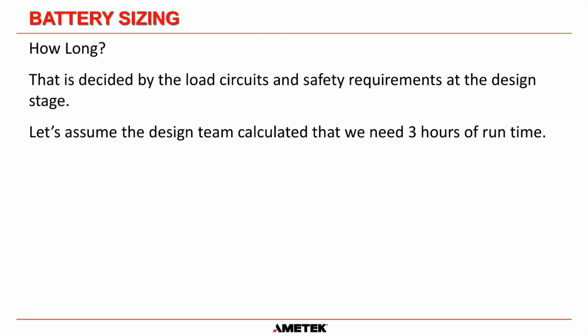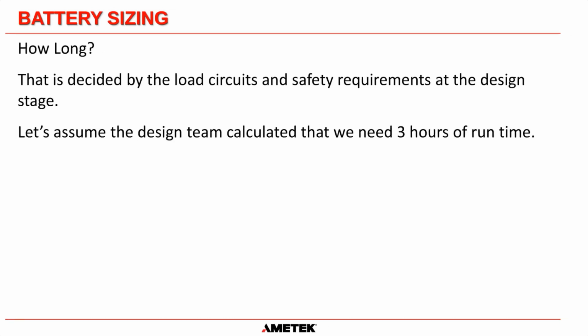But in a petrochemical plant or in a power station, we are doing it more for the safety requirements, where we either want the process to get into a safe mode of operation, or we want the tripping and closing supplies on a DC system to be able to trip and close for a considerable amount of time until the power comes back on again. So if there's any issues while the power is off, the DC can maintain it. So we're going to assume in our calculation that we need 3 hours of runtime, which is a pretty standard value for the petrochem industry.